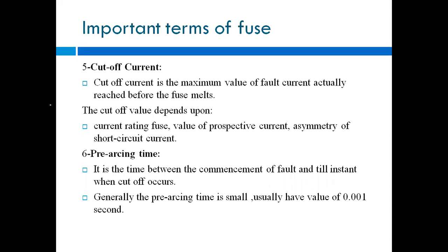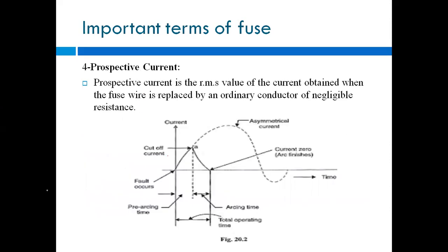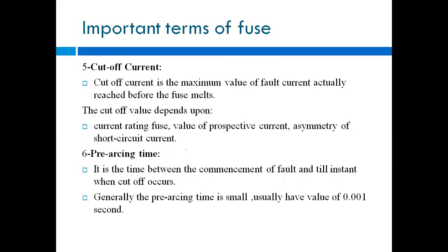From this I also told you that in this pre-arcing period your fuse is not melting. So this cutoff value depends upon the current rating of the fuse, the value of the prospective current, and the asymmetry of the short circuit current. On these factors your cutoff value depends.